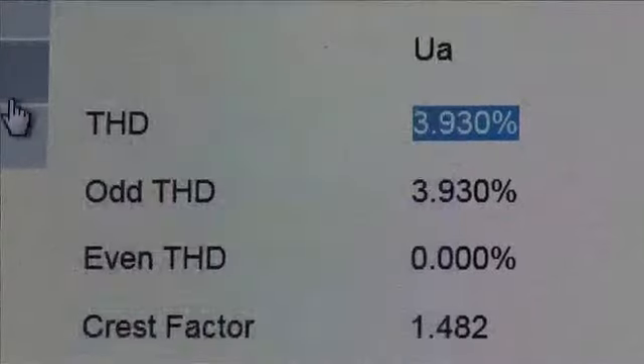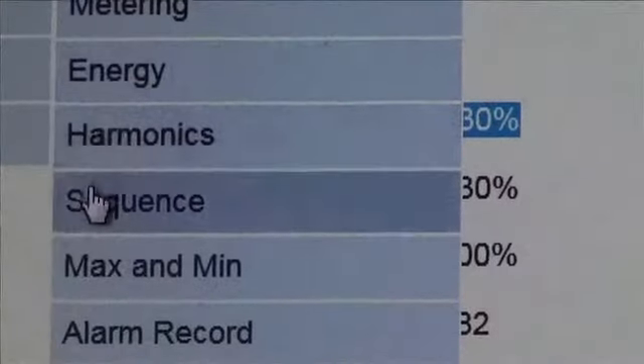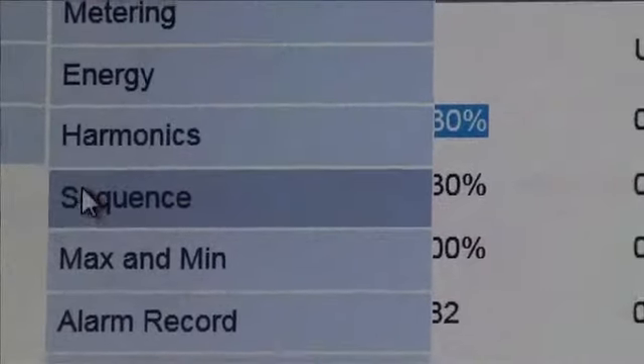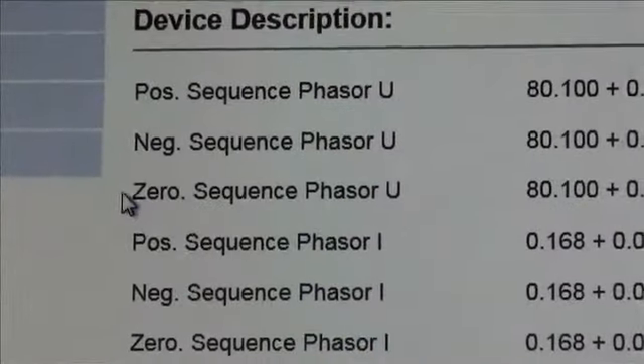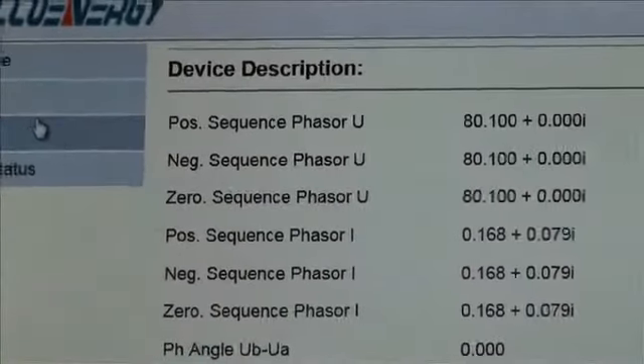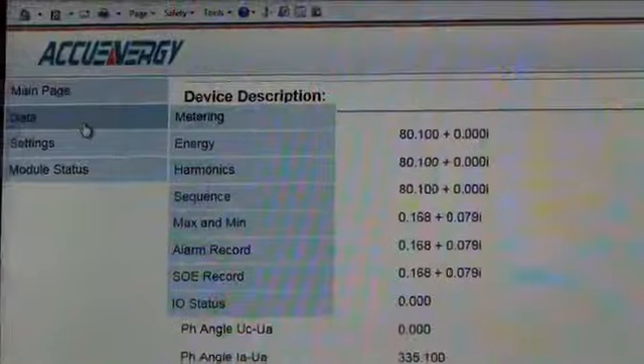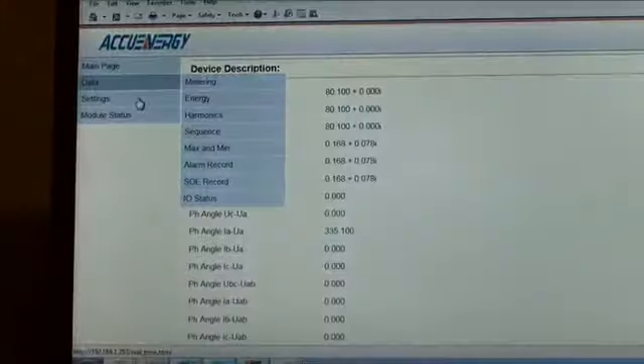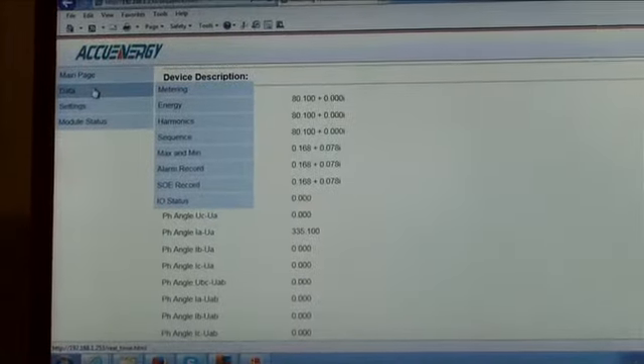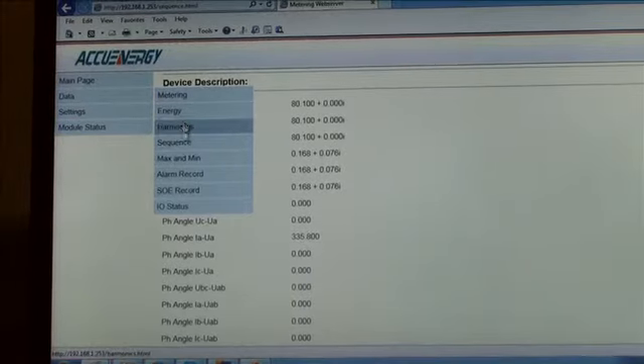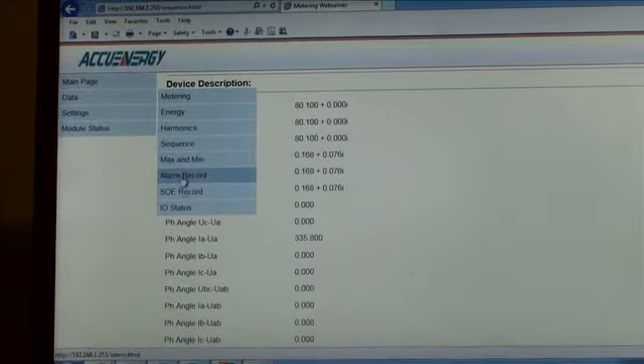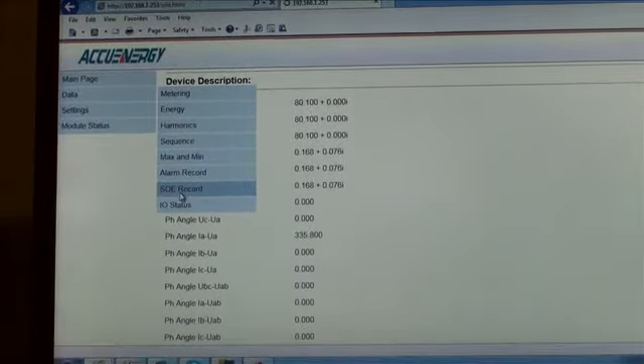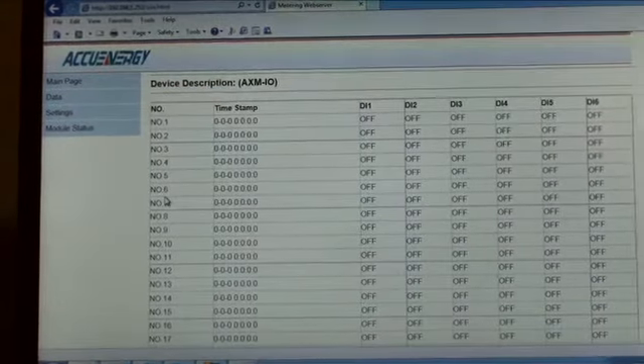We can also monitor the sequence phasor. We monitor by exception over 45 individual components of the power that is being produced. The parameters are set for maximums and minimums, and if it falls outside that range, it sends us an alarm so everyone is notified.